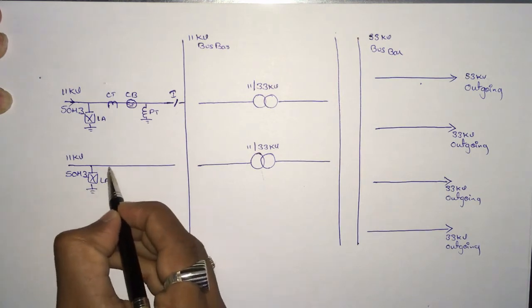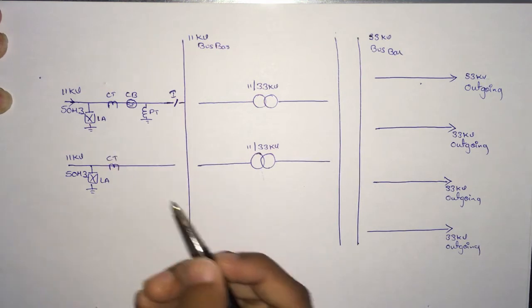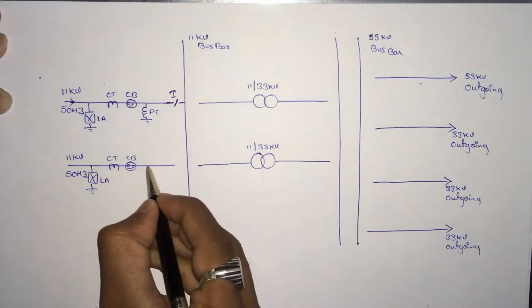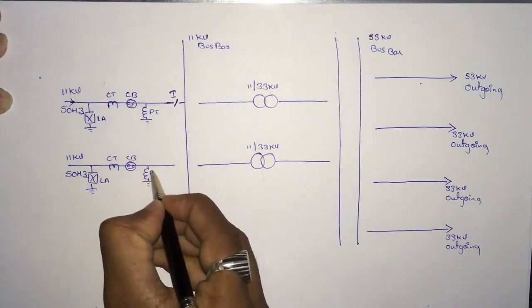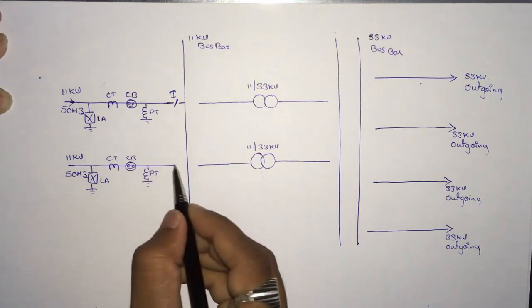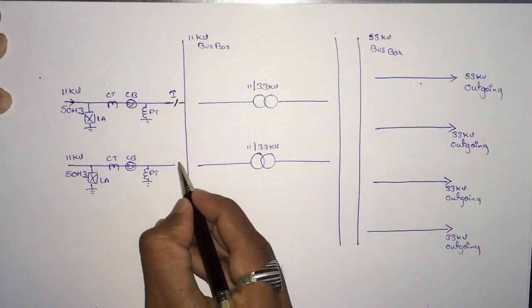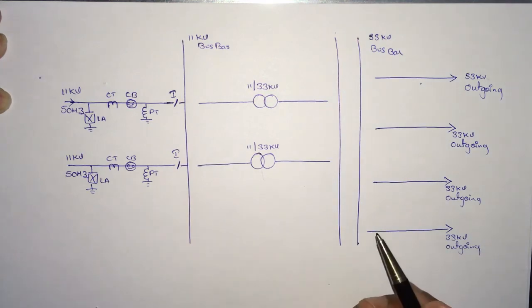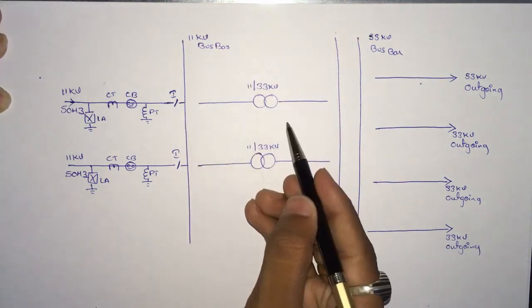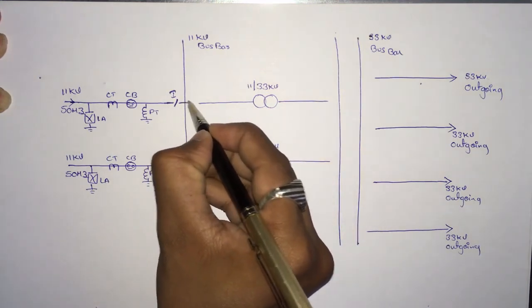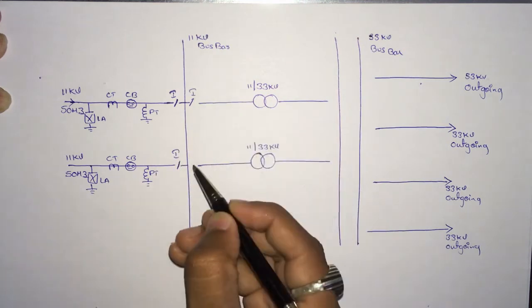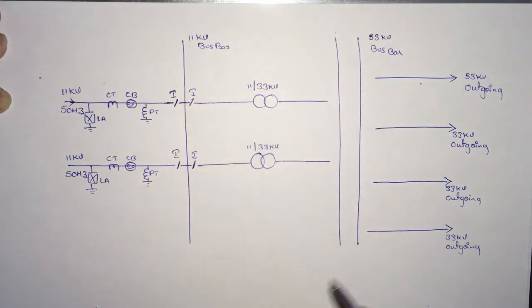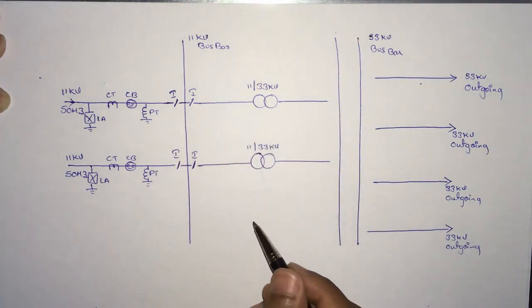Similarly for the second incoming line: LA lightning arrester, CT current transformer in series, CB circuit breaker in series, and PT potential transformer in parallel. Make sure the incoming line is connected to the bus bar with an isolator, not directly. After the bus bar, before connecting to the transformer line, make sure an isolator is placed between the bus bar and the line.